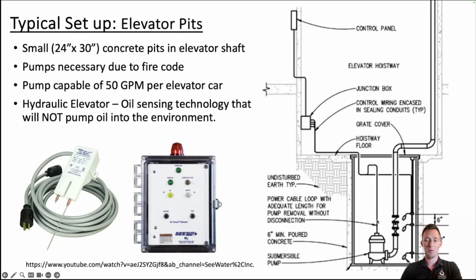I will say, your question may be, when do I do a basin versus a concrete pit? Can I just allow the concrete contractor to pour that pit? If you're in a standard one-car elevator, great. By the time you're into 2 cars, where it's 100 gallons a minute, you may consider doing a fiberglass basin, because our company, for example, that sells everything as a package will understand if that needs to be larger. If you're into 100 gallons a minute, sometimes your pump is taller than 24 inches. So you have a larger pump, you'll need a deeper basin. This basin would have a perforated cover to allow all the fluid through it. If it's a concrete pit, there's typically some grating over top. But that would be how I would decide whether it's a fiberglass basin or a concrete pit.